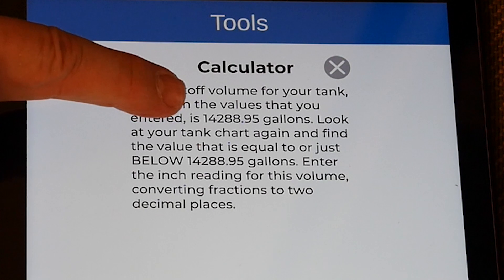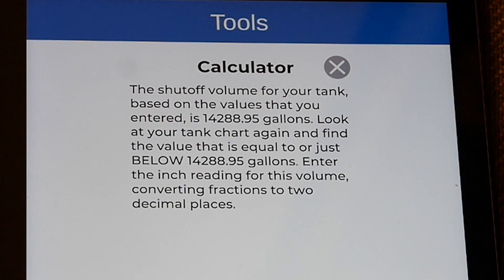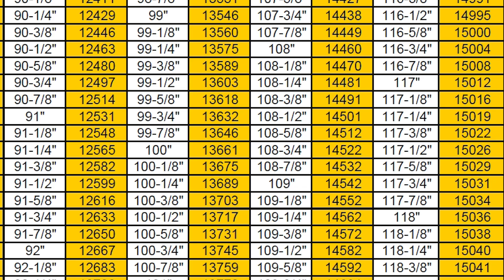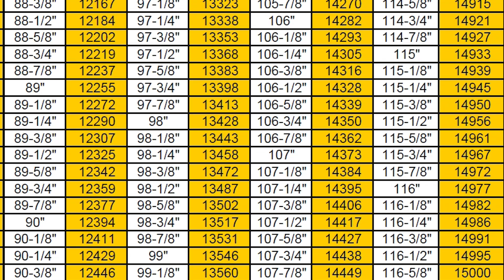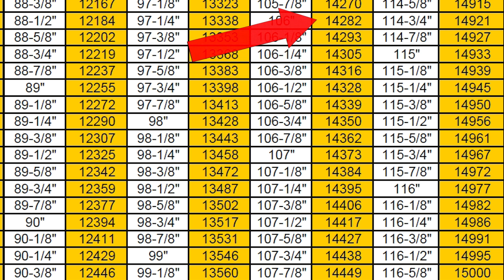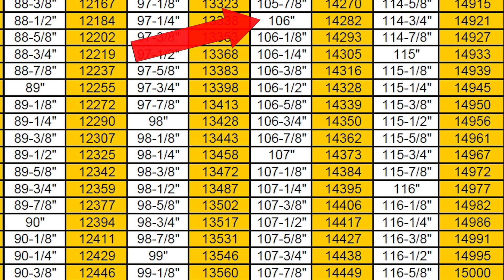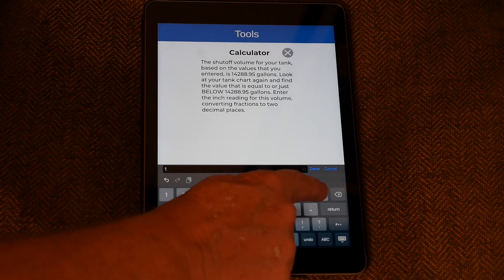The calculator says the shutoff volume for your tank based on the values entered is 14,288.95. I need to look at my tank chart again. I've got a value of 14,293 — but I don't want that one; you don't want to go up, you want to go down. The next one down is 14,282, and that's the one I'm going to use. That tells me to look at the inch reading next to 14,282, which is 106 inches.